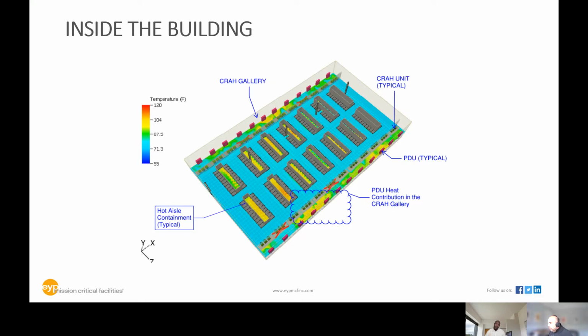You can see the entire room is blue, light blue, which on the temperature range on the left is 70 degrees Fahrenheit inside the cold aisles of the flooded room. The yellow area is the hot aisle, where you're looking at close to 104 degrees Fahrenheit, as expected from the legend. We perform this as a verification that the model will work. This is a data center we recently completed, and it has also been commissioned, and there were no surprises -- it came out the same way it was designed.